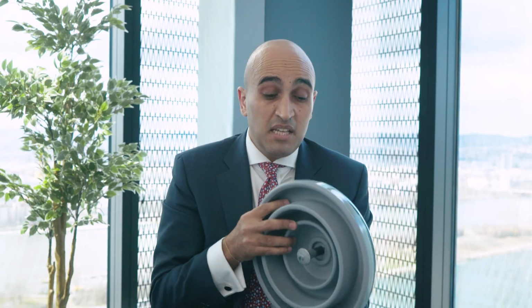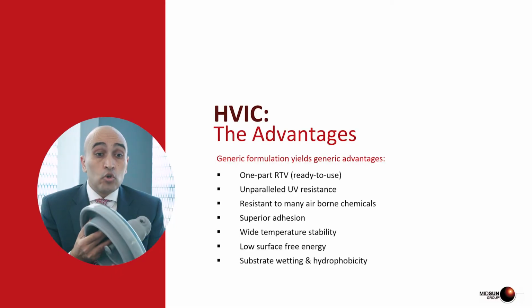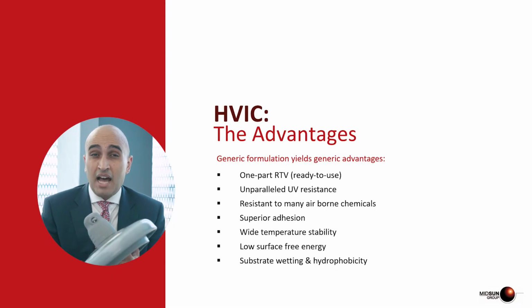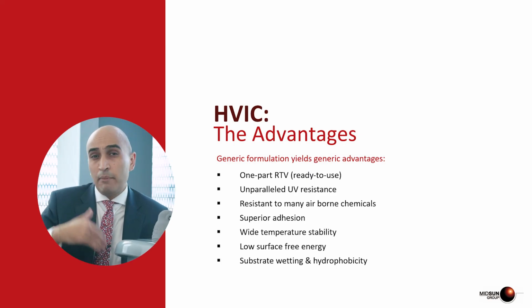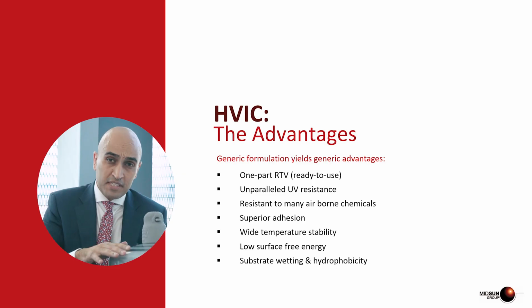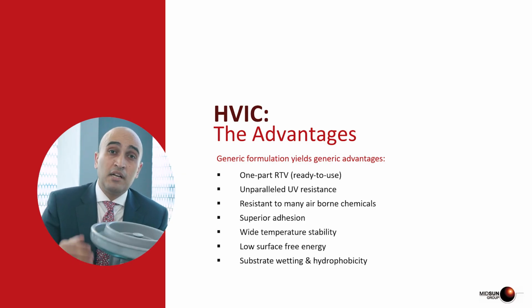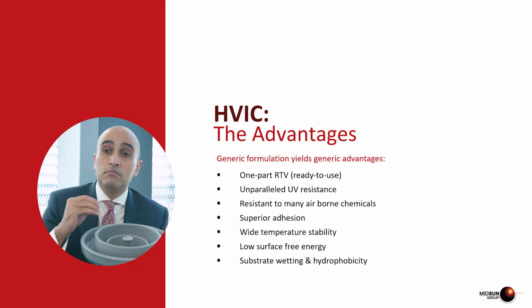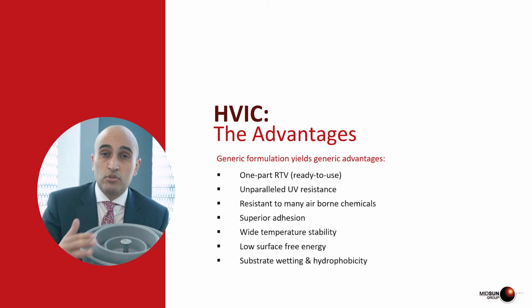This solution has several advantages. One of the advantages of the Midsun RTV coating is that it's a one part system, meaning that it's ready to use, and it's highly resistant to UV radiation. Also, it resists a wide range of temperature, from low temperature -50 to up to 200, and it has low surface energy. The low surface energy will give a hydrophobic effect that will eliminate all chances of production of leakage currents that would lead to flashover. In summary, there are different strategies to mitigate flashover from high voltage insulators, and the most effective one is the implementation of RTV coating.